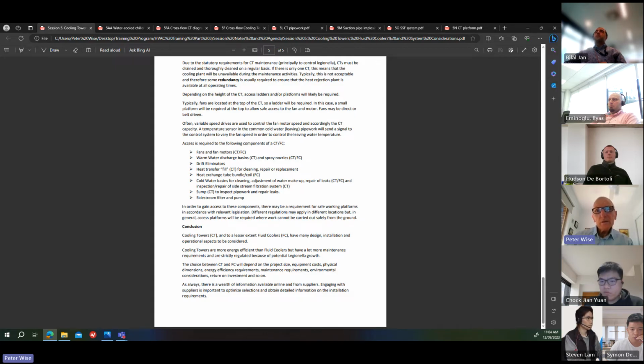And if you can keep the flow through there by using a side stream filtration system, that's going to eliminate your main risk of dead leg. But there could be other situations. Just be aware of it. That's all.